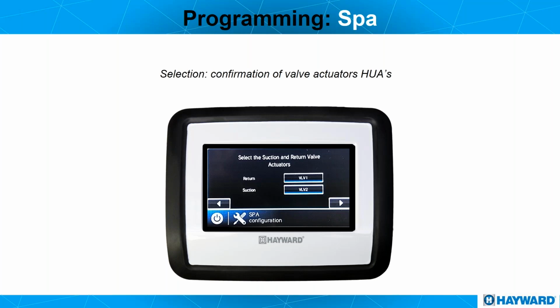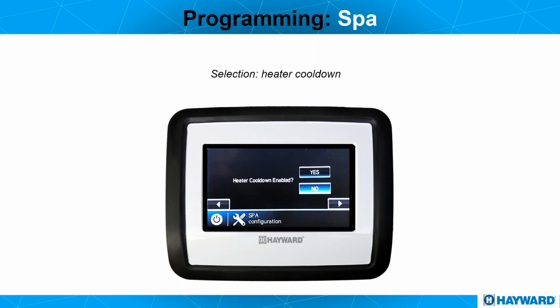Here we see both valves programmed. Valve number one is for the return, valve number two for the suction. Heater cool down, I explained that, it's up to you if you want that. This is in case the pump has to turn off while the heater was running, it'll let the pump run a couple more minutes and shut off the heater so it can cool down the heat exchanger. Same thing with heater extend, in case you have a party. Remember, if the temperature didn't reach the set point, the pump will keep running until it does.